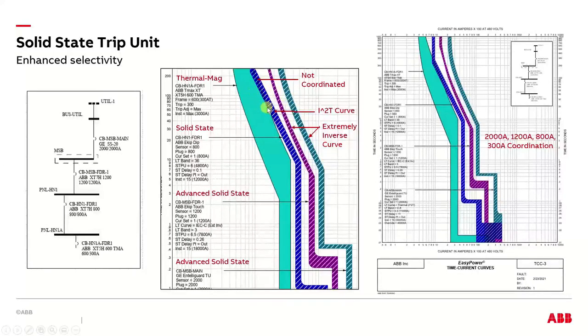So you can see there that this blue standard LSI solid state trip is conflicting with the lighter blue thermal mag breaker. And well, okay, what are you going to do about it? Well, I really can't fit this. I can't make any changes because it's trapped up here and it's trapped down here.